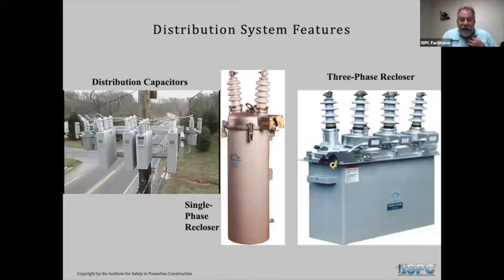Reclosers, we talked to the guys about reclosers because if a fault occurs on a line, a recloser may open up at some interval. Every company is a little bit different, but at some interval, that recloser is going to come back on. And if the fault is still there, it may go out again. And, every company has a different scheme. Some are 12, 15 seconds, some are 30 seconds, but the recloser will come back on. If the fault is not cleared, then it will open up.